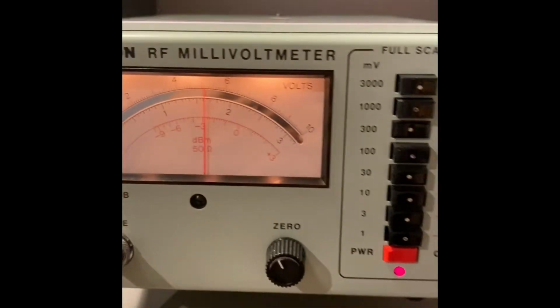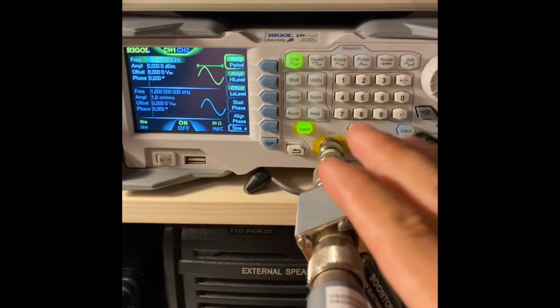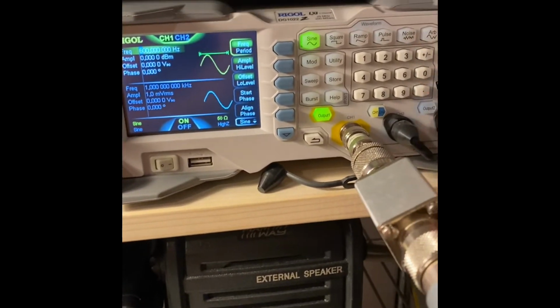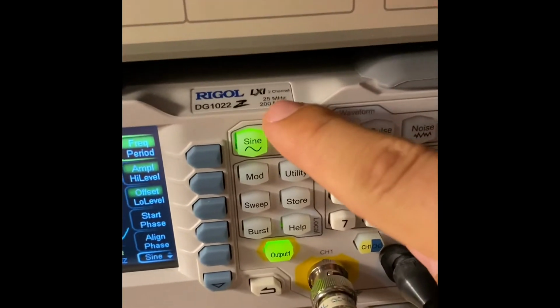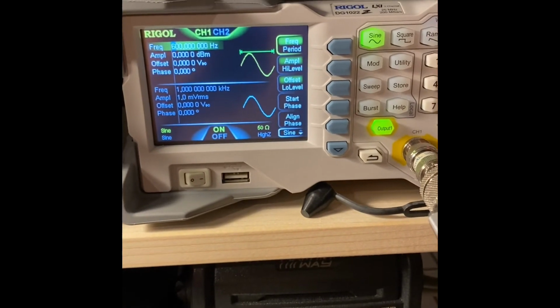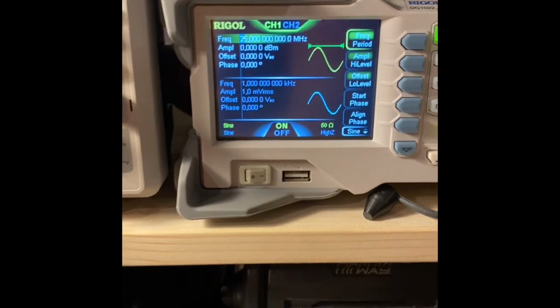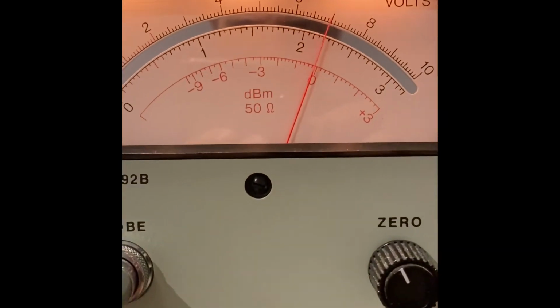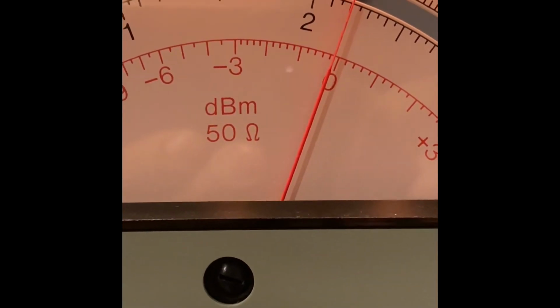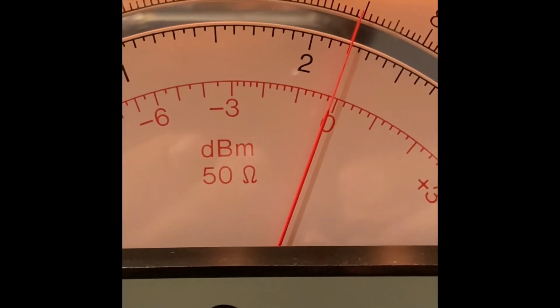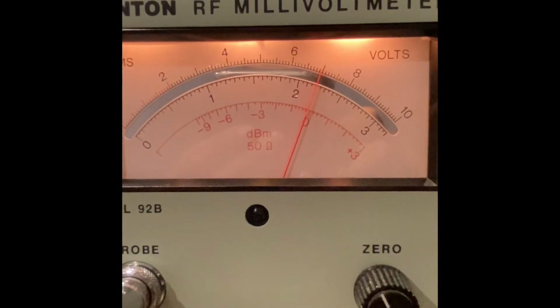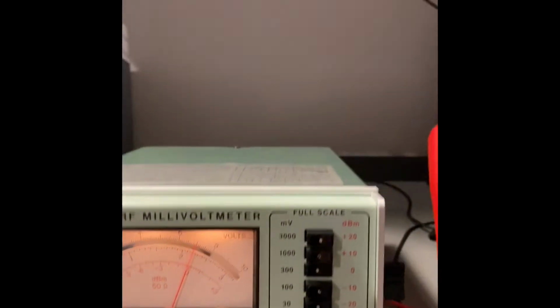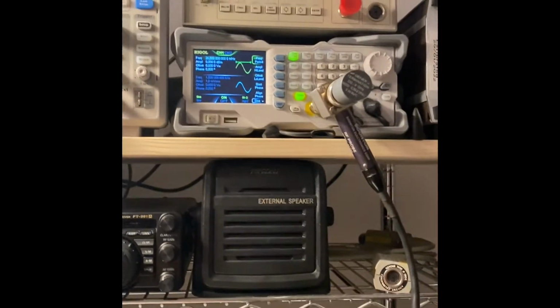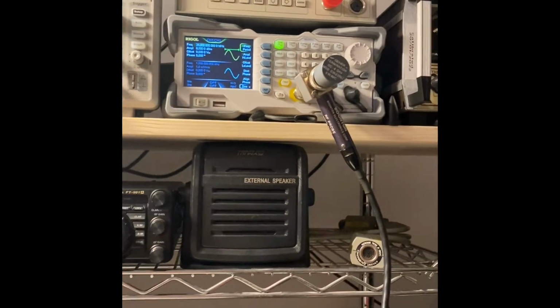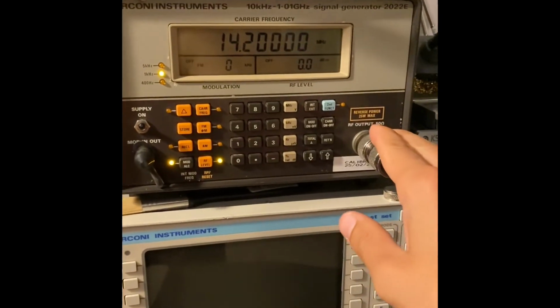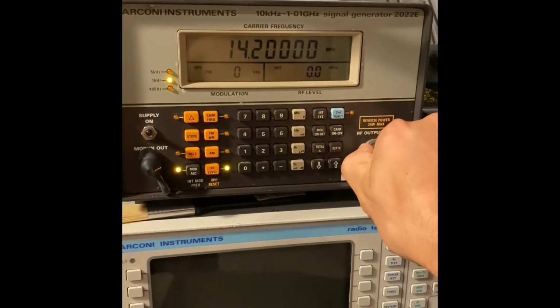Let's go the other way. This generator goes up to 25 megahertz, as you can see here. So let's go up to 25 megahertz, still on 0 dBm. And yeah, 0.1 dB off, so that's good. It could be the generator as well, I don't know. That is new. It's got a certificate of calibration, so I trust this instrument enough. Now I will jump over this to crank the frequency up to 1 gig.